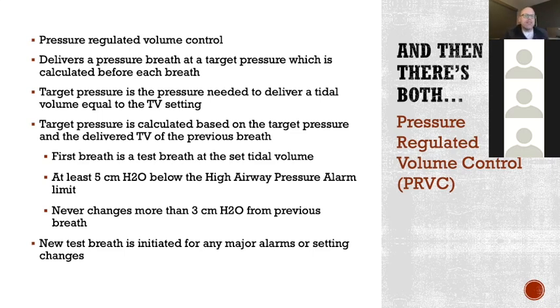As far as the other stuff I have on this slide about the settings, the basics of what you need to know is that it's not going to increase the pressure on most ventilator models within 5 of your high pressure alarm limit. So if I had a high pressure alarm limit on my ventilator set at 30, and the breaths it's giving are taking 23 of pressure, and then it needs to increase it, it's going to alarm out when it hits 25, because that would be within 5 of my alarm limit. It's just something to keep in mind. It might start alarming because of that.